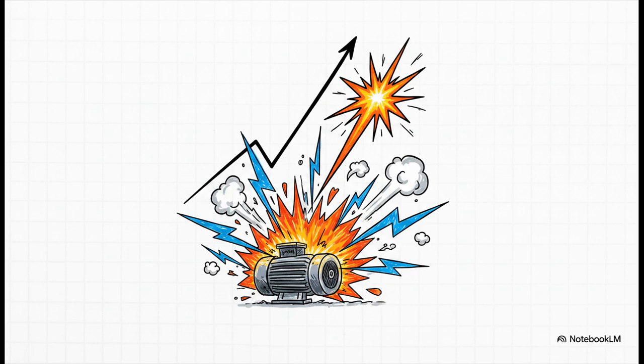If you take a centrifugal pump designed specifically for a 50 hertz system and naively just plug it into a 60 hertz grid, you don't just get 20% more power consumption. Oh no. According to the affinity laws of physics, power consumption increases by the cube of the speed ratio. That is a literally massive power spike. If you move regions, you have to completely recalculate your variable frequency drive parameters and literally shave down your pump impellers, or honestly, you will burn your equipment right to a crisp.